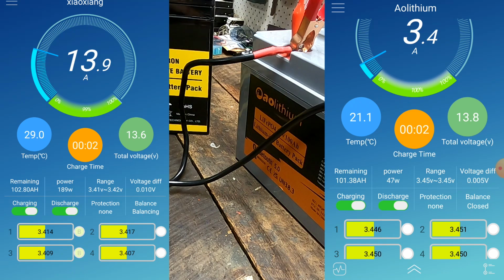Both BMSs are programmed to start balancing at 3.4 volts, but only in the Xiaoxiang is charge balance turned on, so we can already see the balancing happening. Cell number 1, 2 and 3 are balancing, and number 4 is the lowest cell, so it doesn't get balanced at all. There's no balancing happening in the AOLithium battery at the moment, even though we are at 3.4 volts as well, because charge balance is turned off there. So it will only balance once there's no charge measured by the BMS anymore.